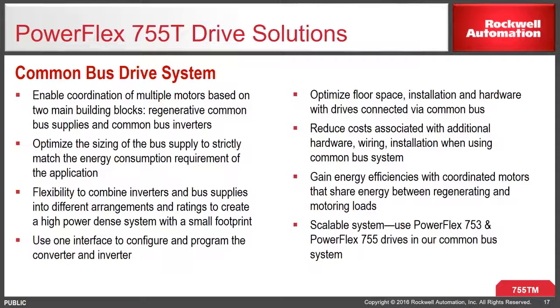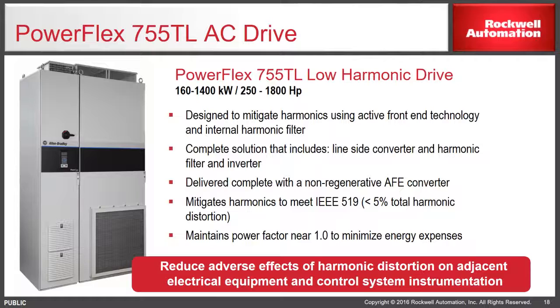The PowerFlex 755TL low harmonic drive solution goes from 250 to 1800 horsepower. It's designed to mitigate harmonics using active front-end technology and an integral harmonic filter. It's a complete solution that includes line-side converter and harmonic filter and inverter. It's delivered as a complete, non-regenerative solution. It mitigates harmonics to meet IEEE 519, that is less than 5% total harmonic distortion. It also maintains a power factor near 1.0 to minimize energy expenses.